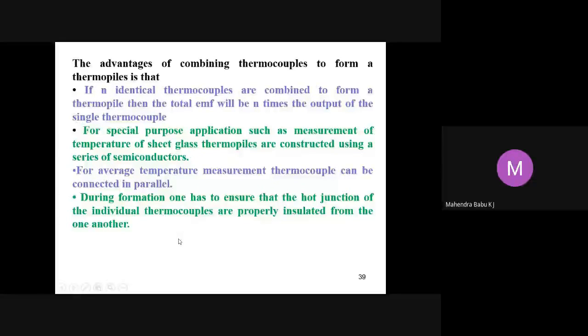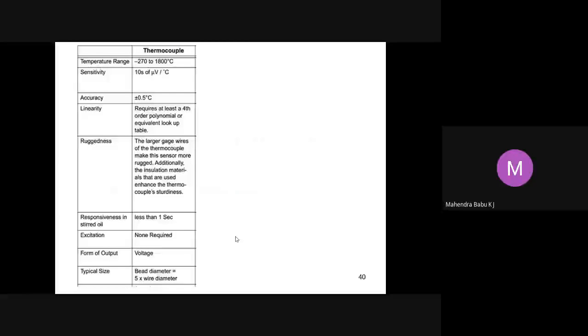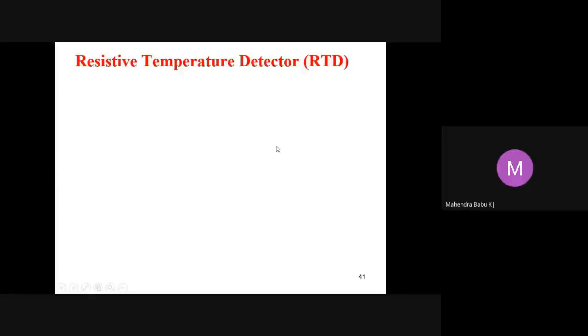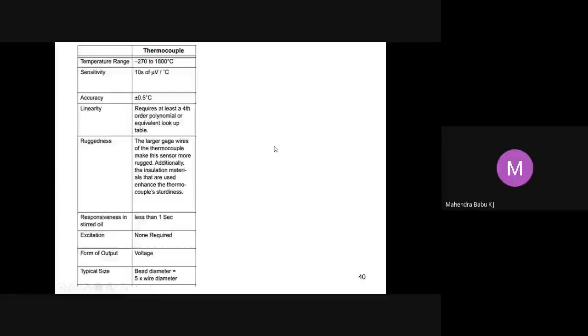you are using thermopiles. And this shows some of the important characteristics with respect to thermocouple, where the temperature ranges from -270 to 1800 degrees Celsius. Accuracy plus or minus 0.5 degrees Celsius, and for linearity, it requires at least a fourth order polynomial or equivalent lookup table. Then the responsiveness is less than 1 second, excitation is not required, and output is usually in the form of voltage. So these are some of the characteristics of thermocouple. Next we can compare this characteristic with other types of temperature sensors.